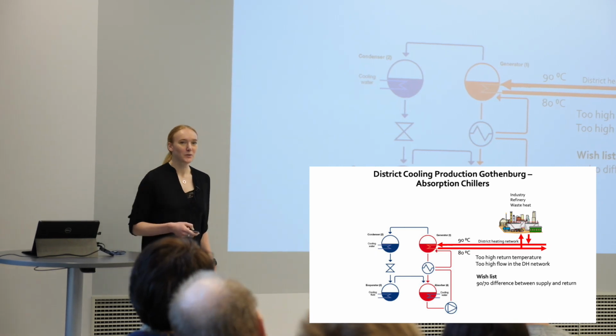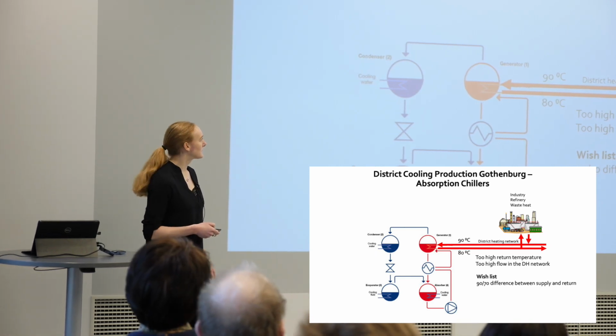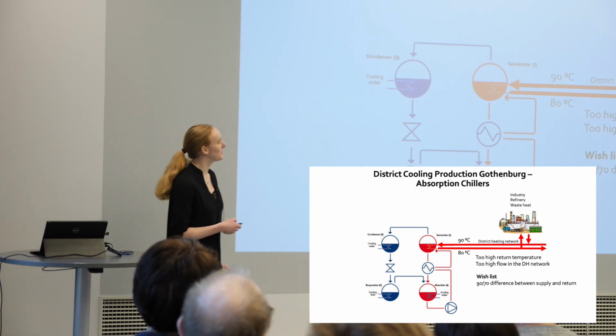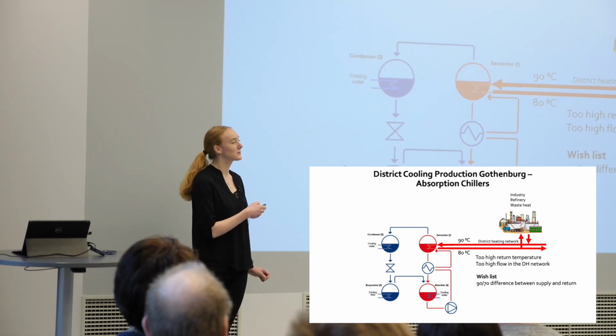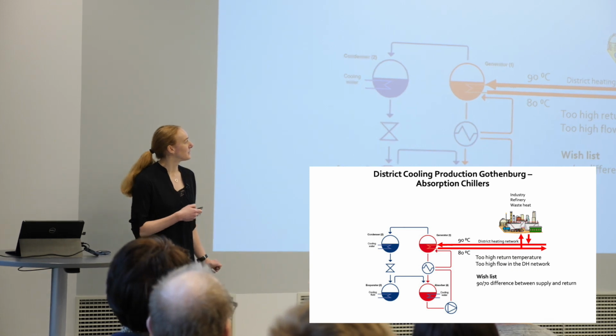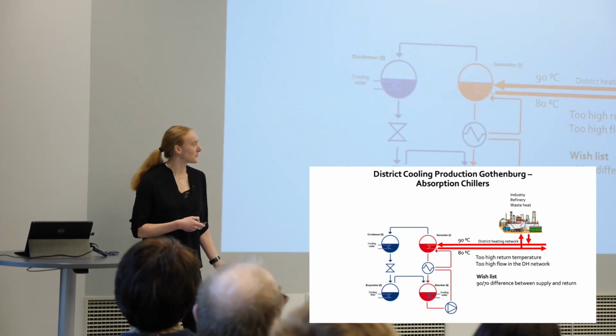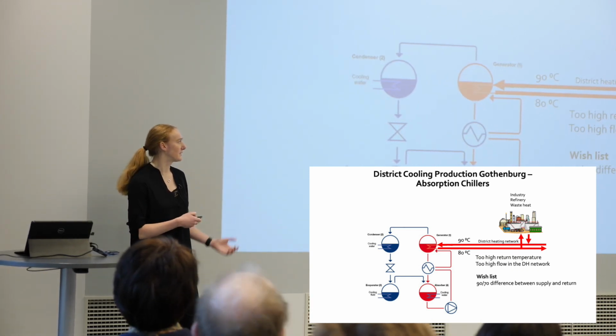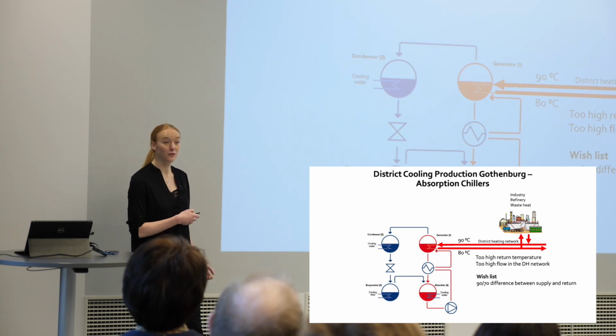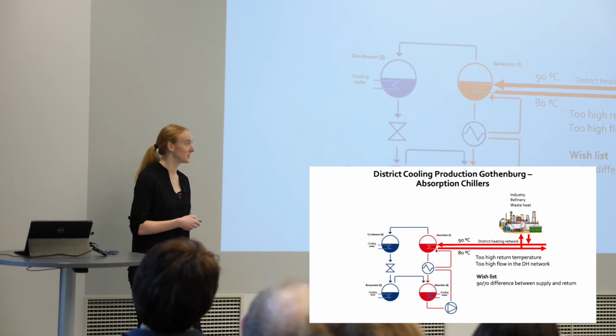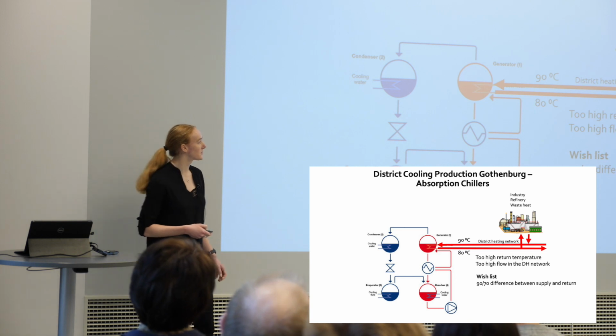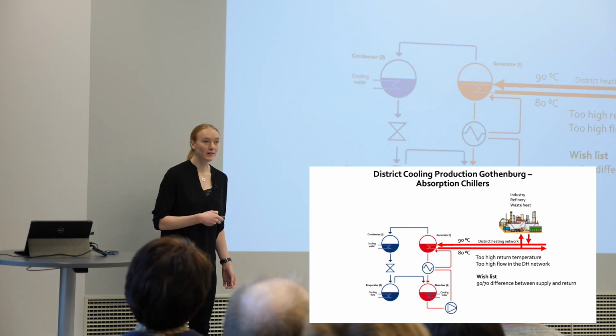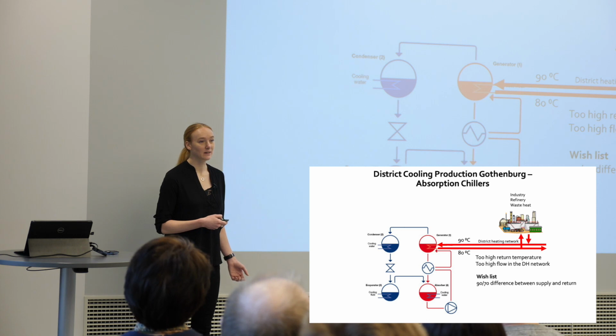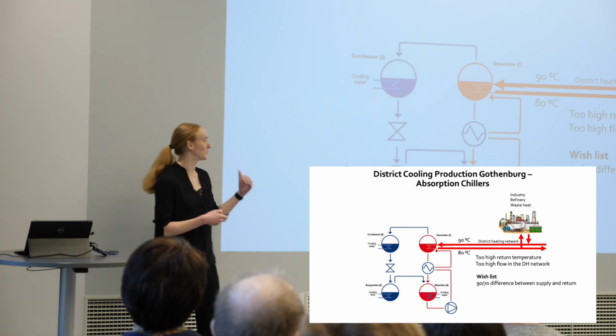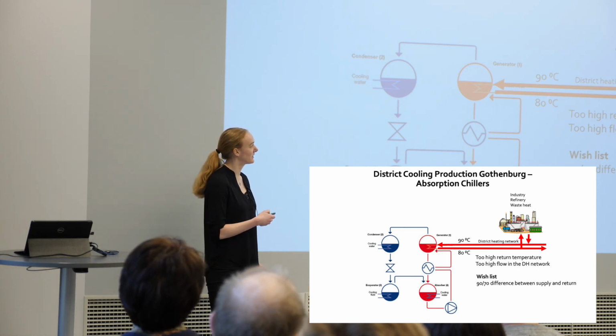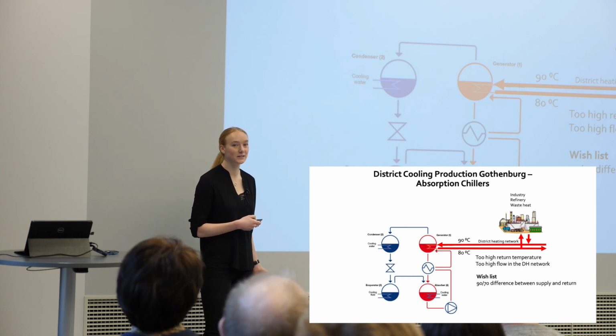And a little bit more on the absorption chillers. There is one issue, although we have a lot of waste heat from the industries, the refineries, the district heating network, it's around 90 degrees of available heat to the absorption chillers. But the absorption chillers return 80-degree water to the district heating network. So the cooling of the water in the absorption chiller is not very high. It's only a delta T of 10 degrees.